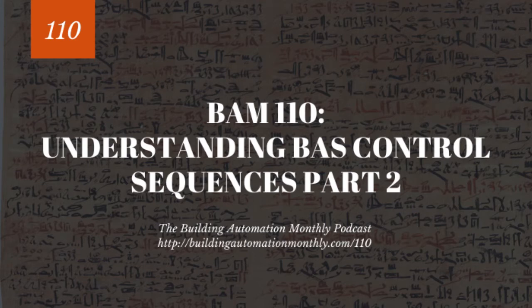All right. Now, as I was saying, we are going to get to the actual sequence of operations. So let me open this up real quick. All right. So taking a look at the sequence of operations, which I will attach to the show notes so you'll be able to see that. I've conveniently organized it in such a way that our enable modes are right at the front for the unit.